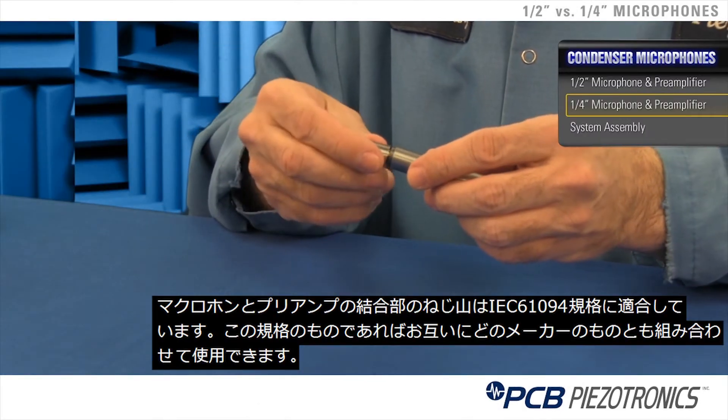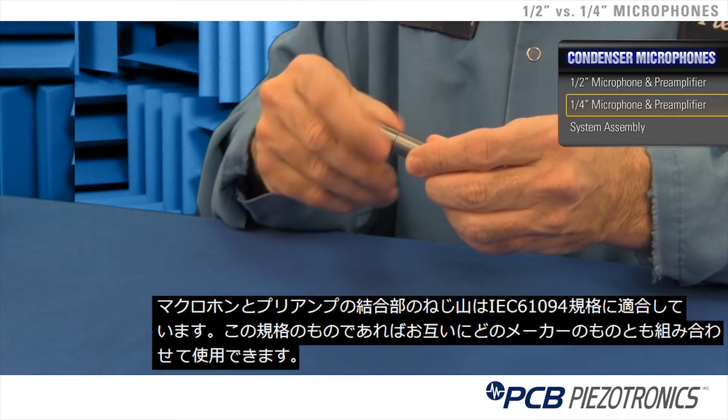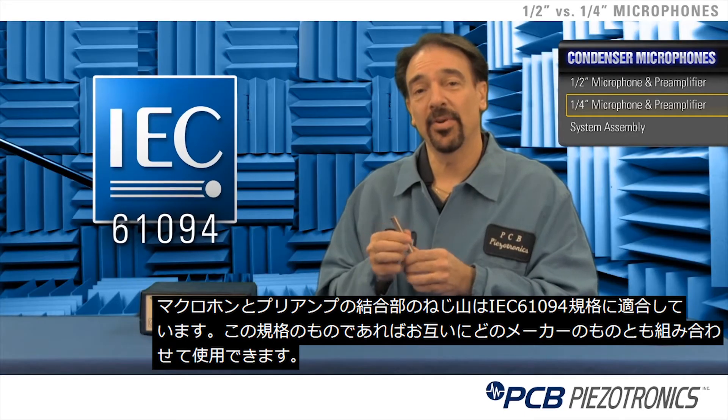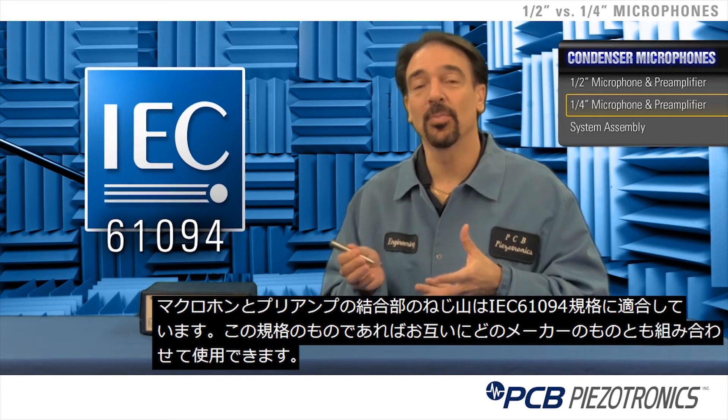The microphone and preamplifier get joined with a standard thread dictated by the IEC 61094 standard. This ensures interchangeability between all manufacturers who comply with the standard.